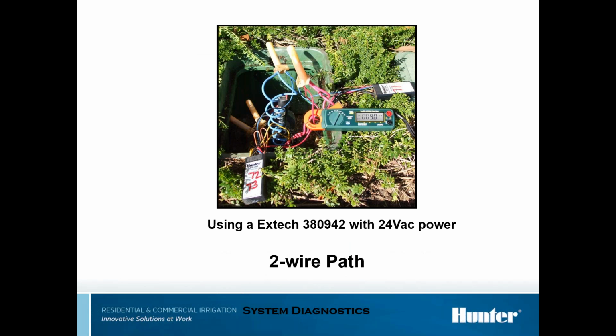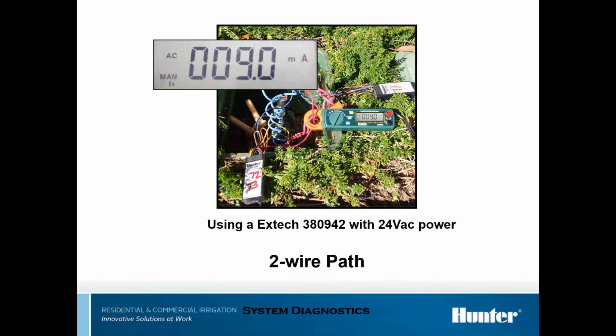On your 2-wire path, from that point, you can use your Extech or your Amprobe PRO-93, PRO-95, your suitable clamp meter, and you can go down your paths. You can do single decoders, and you can also do the whole wire path, but you only want to do one wire at a time. You can see this one is only on one decoder, and it's doing about 9 milliamps, and that's about where it should be. You're going to see slightly differing numbers in some of the slides in here, but typically between 7 and 10 is about where you need to be per decoder.